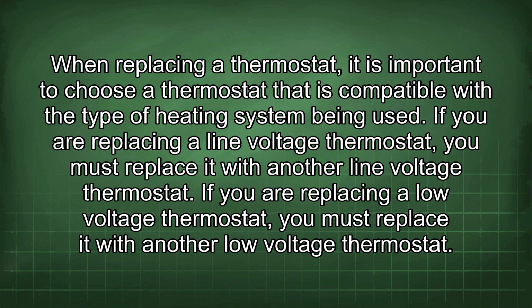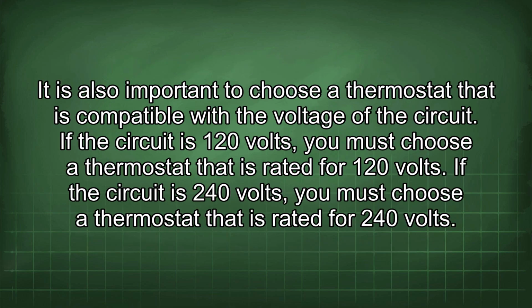When replacing a thermostat, it is important to choose a thermostat that is compatible with the type of heating system being used. If you are replacing a line voltage thermostat, you must replace it with another line voltage thermostat. If you are replacing a low voltage thermostat, you must replace it with another low voltage thermostat. It is also important to choose a thermostat that is compatible with the voltage of the circuit. If the circuit is 120 volts, you must choose a thermostat that is rated for 120 volts. If the circuit is 240 volts, you must choose a thermostat that is rated for 240 volts.